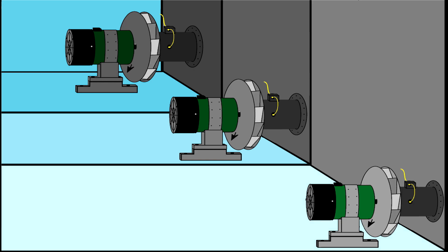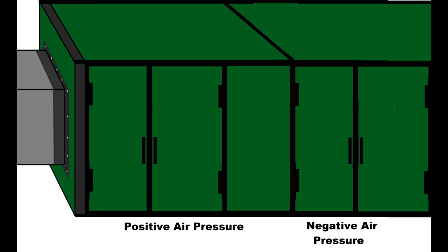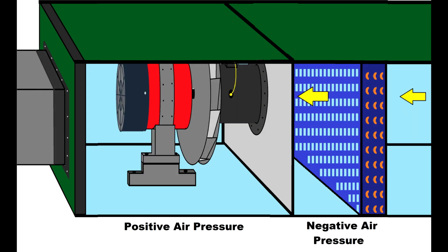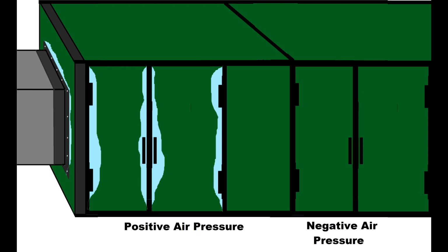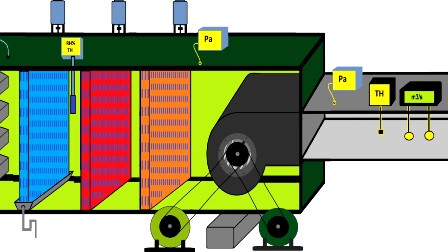So these three fans are good because, as I said, if one fails, the other two will take over. But this type of fan will give a positive air pressure into the supply air chamber, like you see here. It will pull air through the heat exchanger, and then you'll have a positive air pressure, and because of this you might have some leaks through the doors because the volume of the supply air chamber is very big, and what you see in blue is the air leak, so you can have air leaks all over the place.